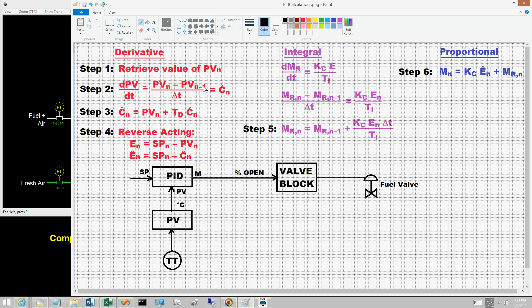If time 0 is the time the controller was switched to auto, then iteration n occurs at n times delta t. With today's processors, the norm is sampling times of one second or less. For the slow processes typical of the process industries, such sampling times do not introduce significant errors into the calculations.